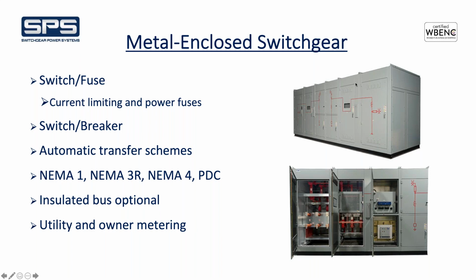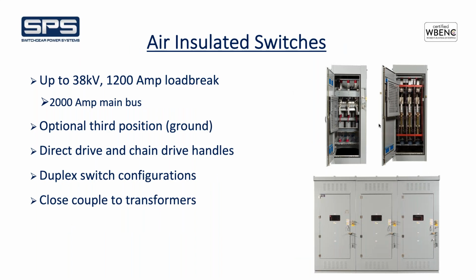So it was a two-sided, two utility feeds, just a mirror image of each other. But that is an example. That was 38 kV of metal enclosed circuit breakers. So in our metal enclosed design for the switches, we offer air insulated switches and gas insulated. This slide is focused on the air insulated switches. I mentioned up to 38 kV 1200 amp load break switches. We do offer a third position switch for maintenance grounding. Very convenient for the maintenance personnel to utilize that rather than external ground cables, different operating handles. This unit right here, this was actually a 38 kV unit for a solar farm that we did a couple years ago, but a traditional metal enclosed switch fuse.